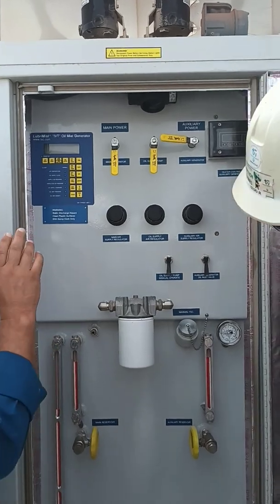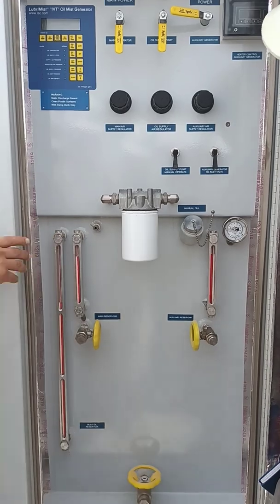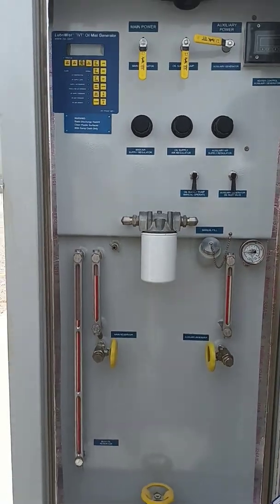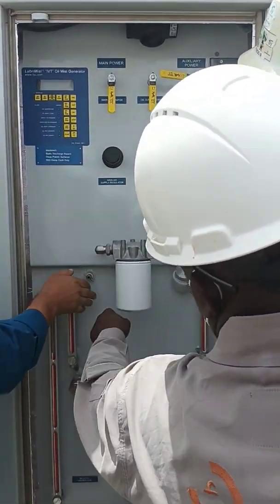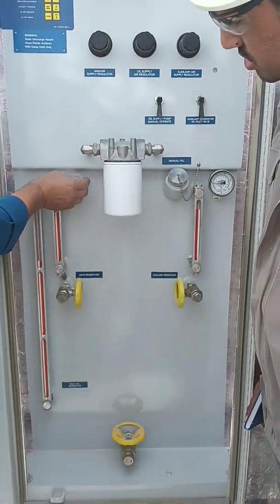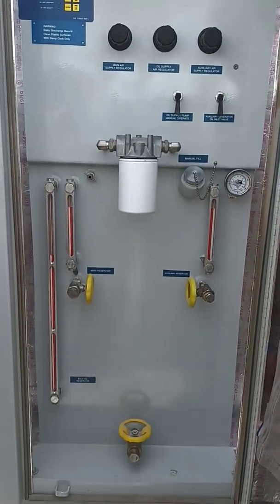So 50 millibar is the pressure above the oil level in that pipe. If you put a gauge into the 2-inch pipe, or you put a gauge on the manifold on the pump, you will get 50 millibar. So this is the oil mist pressure. So what do you think that's for? The oil mist inspection valve. So you can see the mist here. Okay, inspection only. Yeah, just to have a look at it.